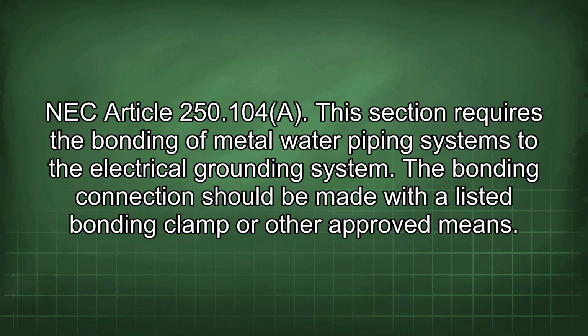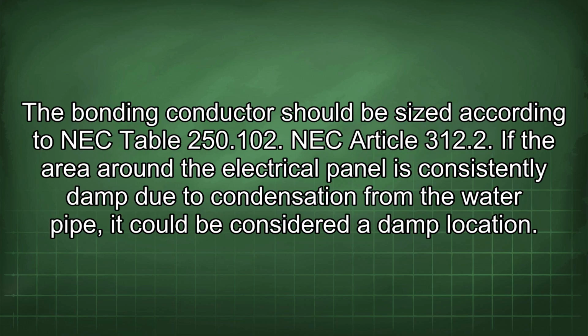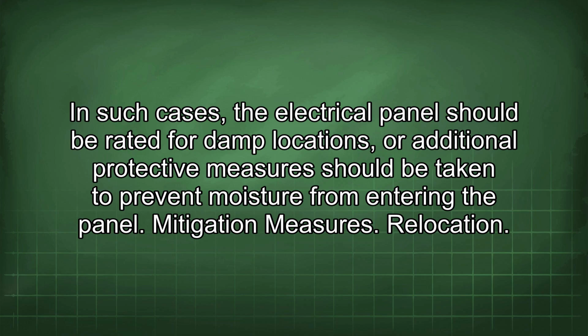NEC Article 250.104(A). This section requires the bonding of metal water piping systems to the electrical grounding system. The bonding connection should be made with a listed bonding clamp or other approved means. The bonding conductor should be sized according to NEC Table 250.102. NEC Article 312.2. If the area around the electrical panel is consistently damp due to condensation from the water pipe, it could be considered a damp location. In such cases, the electrical panel should be rated for damp locations, or additional protective measures should be taken to prevent moisture from entering the panel.